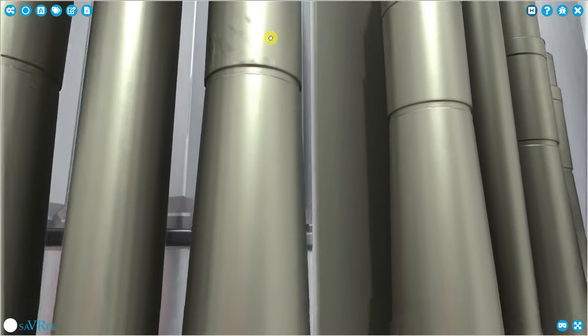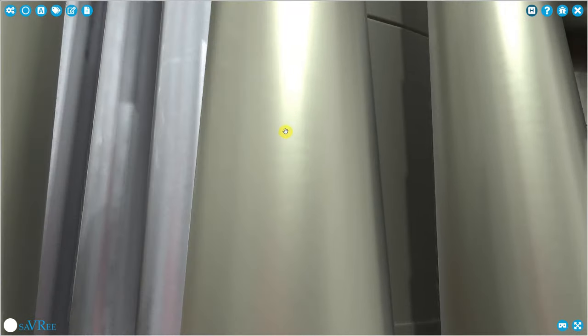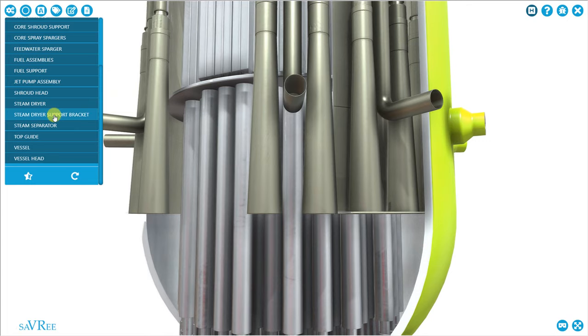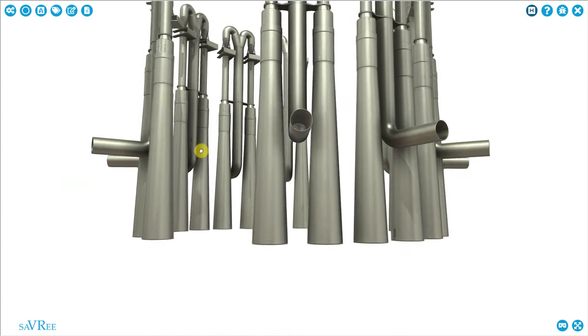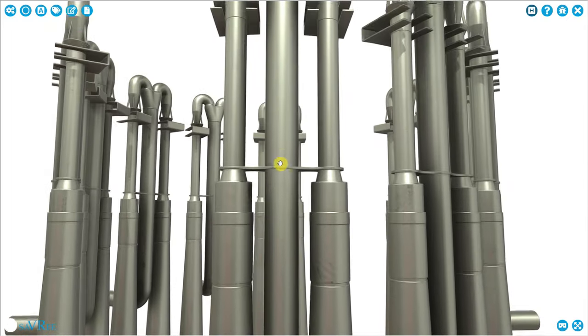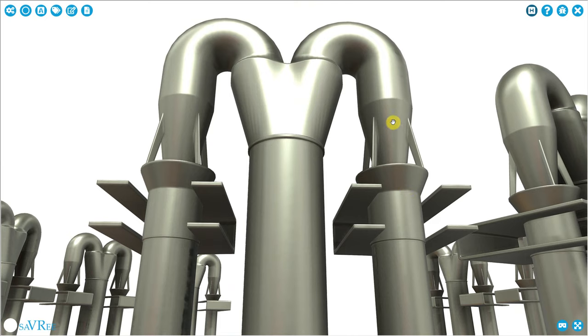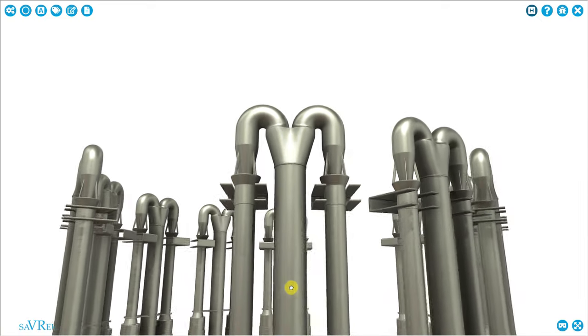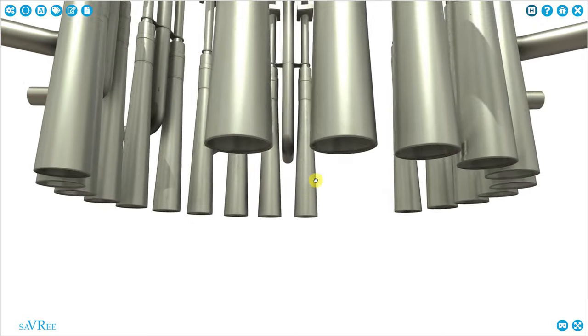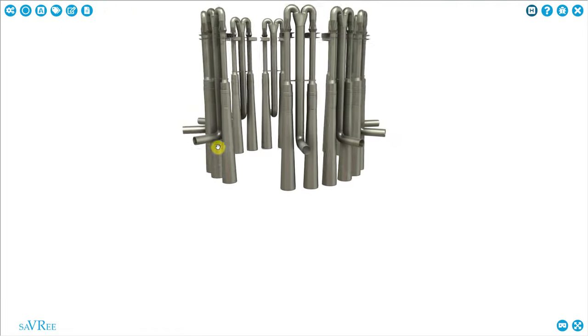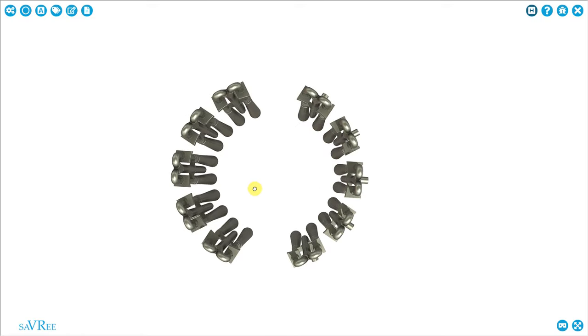So we'll mix those two together. About a third of what passes into the mixing tube is recirculation water, with the remainder being feed water. The water that's mixed comes down here and passes out of a diffuser. You can see it there. In fact, if we use our configurator again, we can have a better look. So you can see that the water would enter through this pipe, comes up through the riser, it splits off. That's our recirculation water that splits off, comes down through the nozzles, and is sprayed at high velocity into the mixing tube or the mixing pipe. And from the sides, then we draw in our feed water. When the feed water and the recirculation water is mixed, we will discharge that mixed water out of our diffusers. And there's two of these per jet pump. You can see the shape of the jet pumps here. They're evenly spaced around our main reactor core.